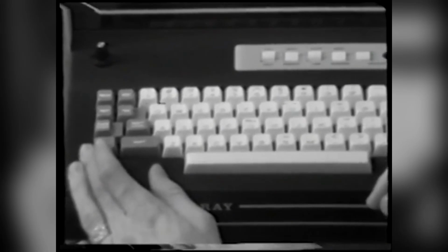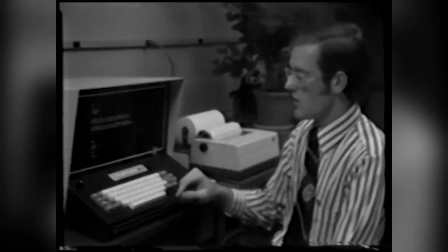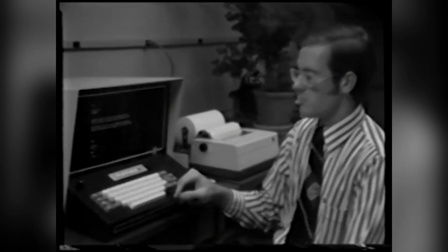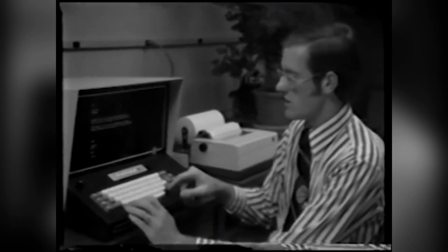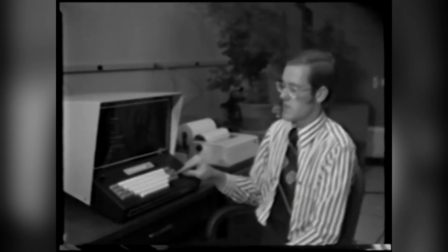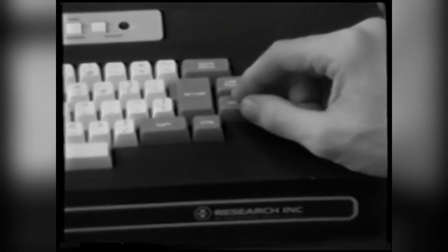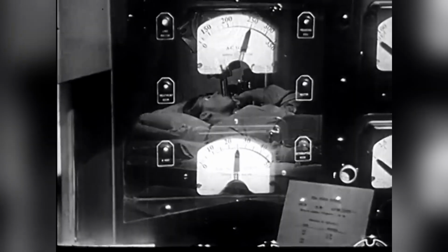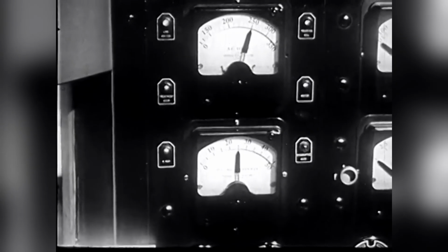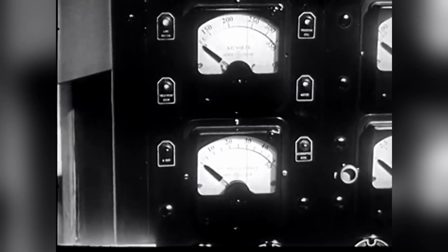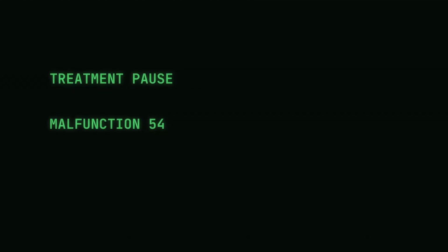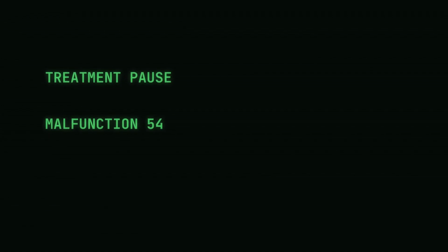Noticing that she had typed the letter for X-ray mode instead of the letter for electron mode, she moved the cursor up, corrected the single character, and pressed the return key several times to bring the cursor back to the command line. All of that took her less than 8 seconds. Her screen reported the parameters verified and the beam ready, so she turned the beam on. Within a few seconds, the machine stopped itself and displayed the words, "Malfunction 54."